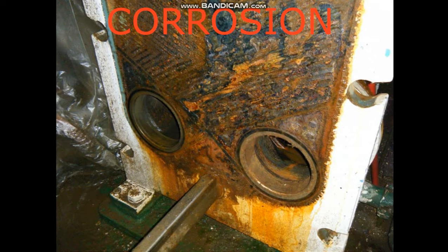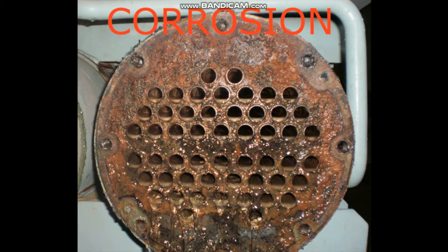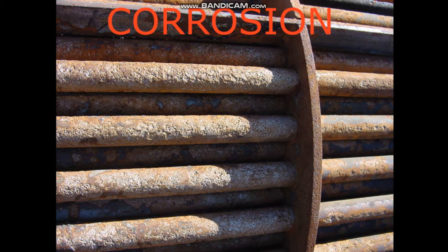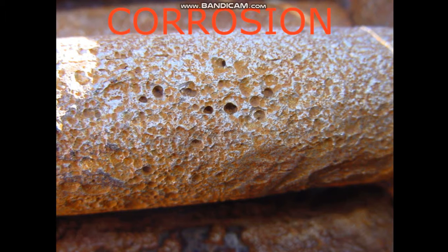Corrosion fouling is classified as a chemical reaction which involves the heat exchanger tubes. Many metals, copper and aluminium being specific examples, form adherent oxide coatings which serve to passivate the surface and prevent further corrosion.